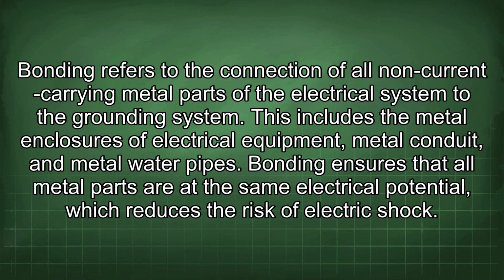Bonding refers to the connection of all non-current carrying metal parts of the electrical system to the grounding system. This includes the metal enclosures of electrical equipment, metal conduit, and metal water pipes. Bonding ensures that all metal parts are at the same electrical potential, which reduces the risk of electric shock.